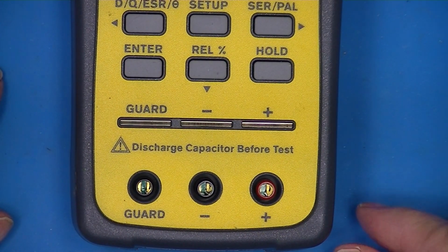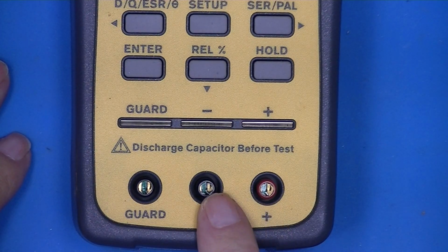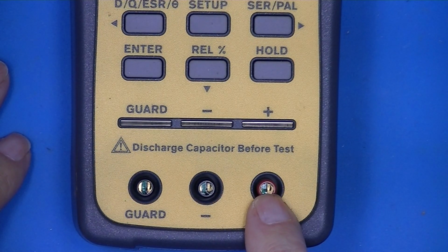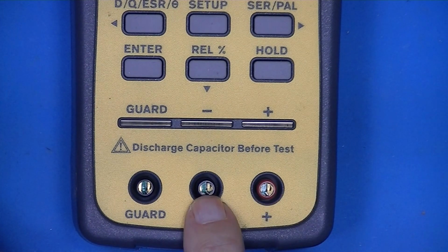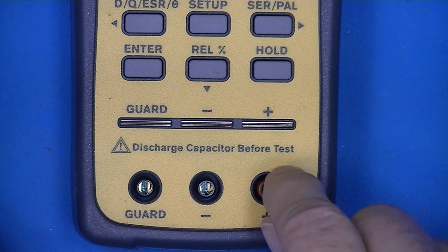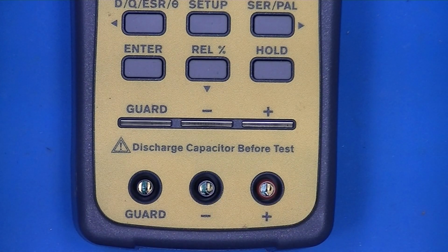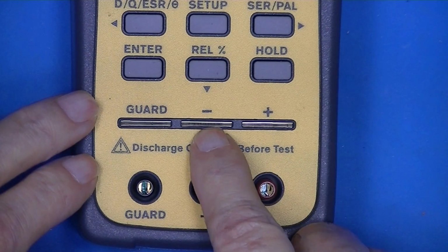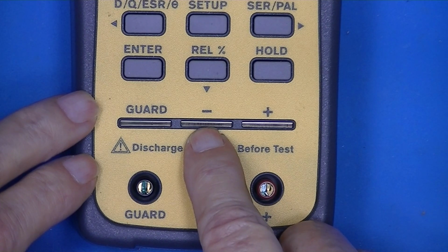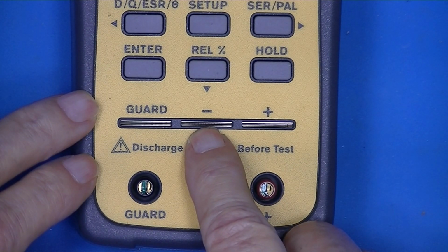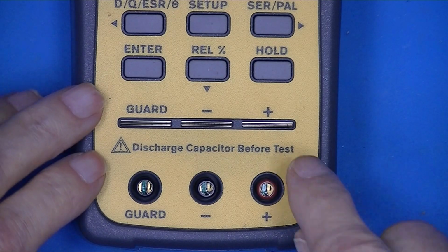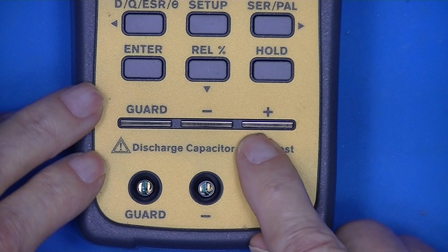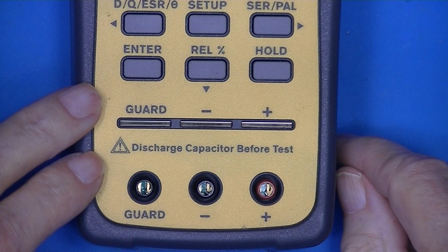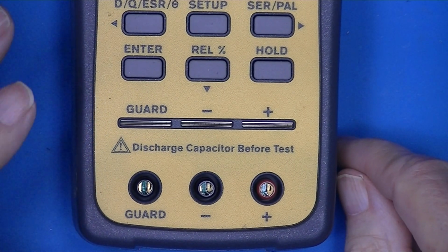This is capable of 2-wire or 4-wire measurements. If I plug a set of standard test leads in here with points on one end and a banana plug on the other, plug goes in here, that becomes a 2-wire measurement. If I plug something in here, it could be a 2-wire measurement external to the meter. It's a 4-wire measurement inside the meter. I'll explain to you how that happens in a minute.